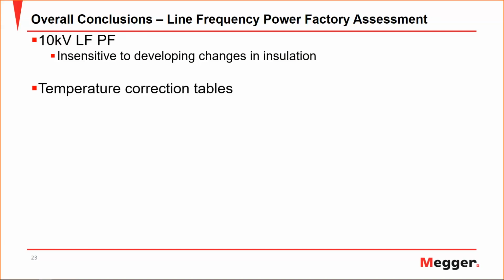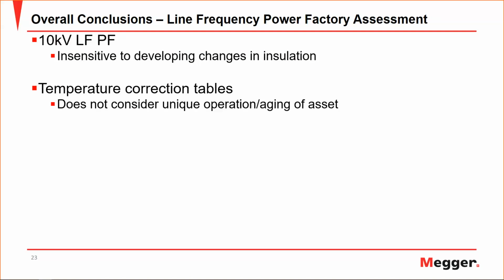Next, temperature correction tables do not consider the unique operation or aging of the asset, and this leads to inaccurate correction of line frequency results. In addition, temperature correction tables only exist for line frequency. So if you are going to try and correct frequencies other than line frequency, the standards have no solution and you must use ITC.